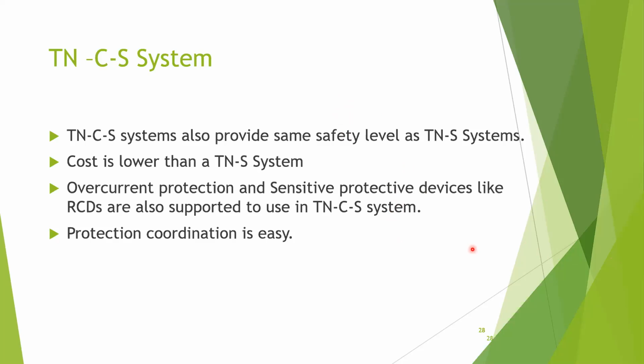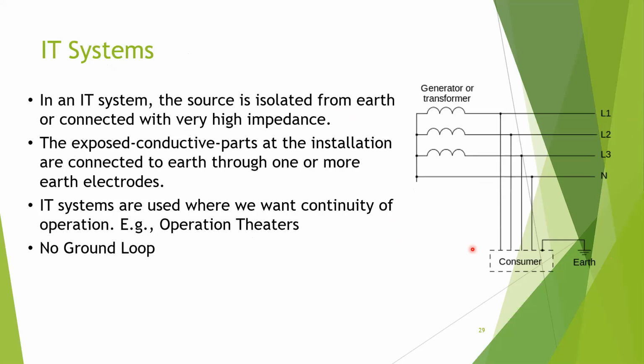No worries. And now we are coming to the IT system. The IT system is special because this is the only system where we do not have a source-side earth; the source side is isolated. So what happens in the IT system is there's no complete circuit for current to flow. Even if you have an earth fault here, the earth fault is not continuing to the source.